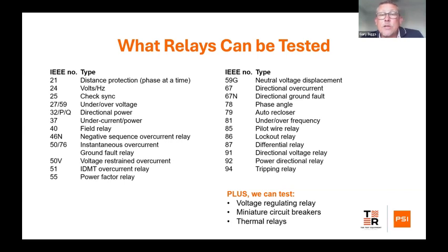As I said, in addition to those IEEE numbers, we can also do voltage regulating relays, miniature circuit breakers, and thermal relays. One of the things, again, is that we have two channels, and both channels will give us either voltage or current, which allows us to test, as you can see, a very wide selection of relays with one little test set.